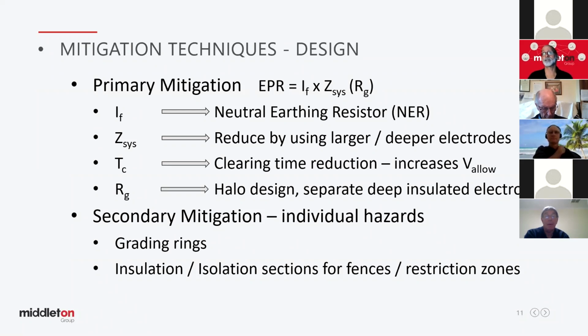So if you take a separated, deep insulated electrode, drive it 30 metres in the ground with only the bottom 5 metres exposed to the earth, you're effectively pushing your current deeper down into the ground. The top part of the electrode is PVC insulated, so the current doesn't leak into the ground at the surface and cause voltages of the earth there. So it's just another specialised technique.